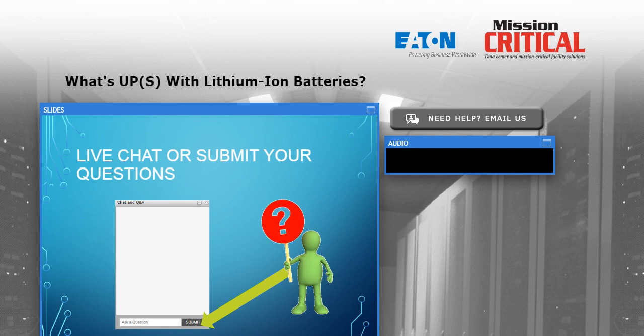Do you recommend installation of these type of batteries inside the same room that contains a generator? Don't see any problem with that as long as the ventilation requirements for the generator are met. And also you do want to keep an eye on temperature. So maybe the generators are running during an environmental event for a week, for example. Is the heat going to build up in that room where it might get too warm for the batteries? But again, these batteries do better at higher temperatures, certainly in the short term without significant damage, than traditional UPS batteries. But you do not want to ignore the temperature limits or subject the battery to extended high temperatures, because it will impact their 10-year service life.